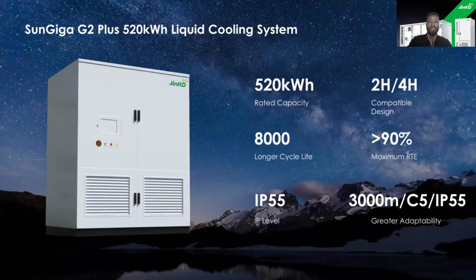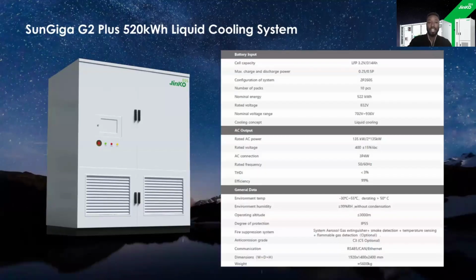Looking at the specifications: again a 314 amp hour cell, able to run as a 2-hour or 4-hour system, 0.25 or 0.5P. There are 10 packs within the system, 5 and 5 side by side. It runs at 400 volt AC, with the same operating environmental temperature range of -30 to +55.